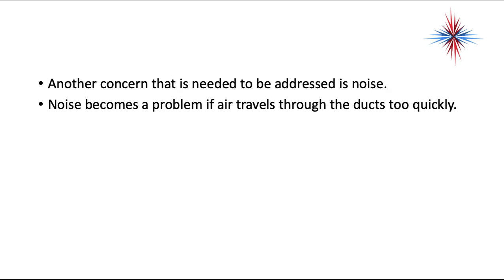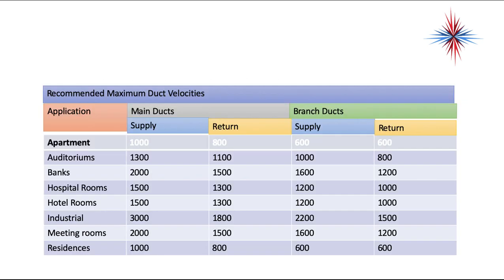We also have to worry about noise. Noise becomes a problem if air travels through the ductwork too quickly, so this has to do with the speed of air — feet per minute. We have recommended maximum duct velocities. For residential main ducts, no more than 1,000 feet per minute for supply or 800 feet per minute for return. For branch ducts, supply and return, 600 feet per minute.